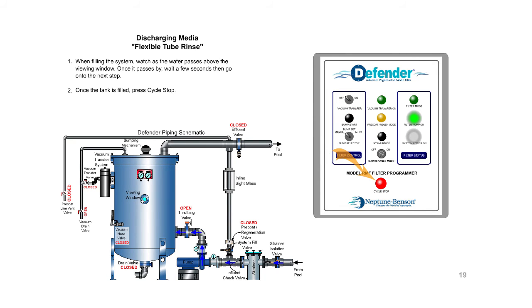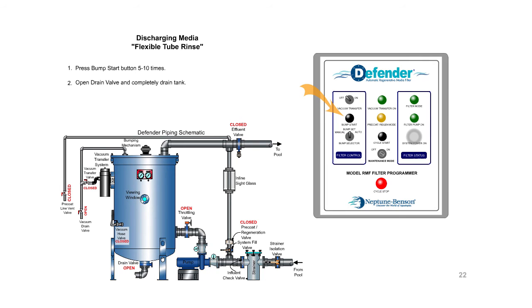When filling the system, watch as the water passes above the viewing window. Once it passes by, wait a few seconds, then go on to the next step. Once the tank is filled, press cycle stop. Turn bump selector switch to bump set. Press bump start button 5 to 10 times. Open drain valve and completely drain tank.